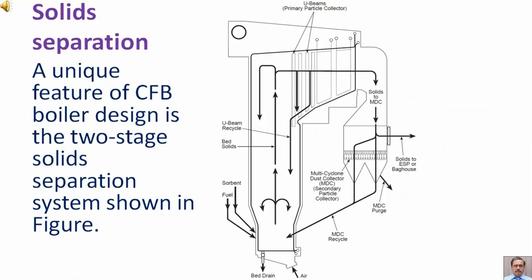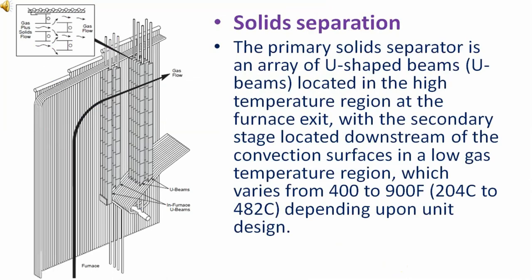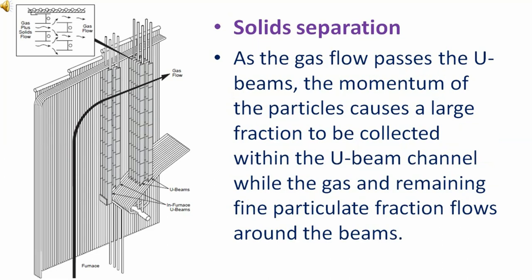Solid separation. A unique feature of circulating fluidized bed boiler design is the two-stage solid separation system shown in figure. The primary solid separator is an array of U-shaped beams, that is U-beams, located in the high temperature region at the furnace exit, with the secondary stage located downstream of the convection surfaces in a low gas temperature region which varies from 400 to 900 Fahrenheit depending upon unit design.